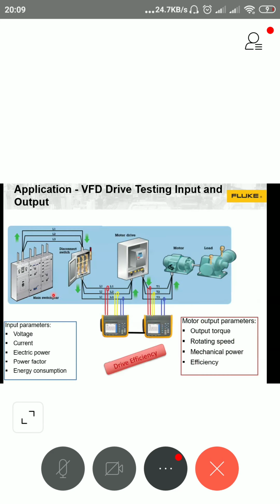And what are the major applications? When it comes to a VFD, checking the VFD efficiency is important, and monitoring the input side and the output side is also important. A single equipment can be used. You can connect to the VFD input side and do a power analysis, and similarly you can take the equipment and connect to the output side and do the power analysis. And if you want to check the efficiency, the best solution is connecting two equipments, synchronizing them, and checking the drive efficiency.